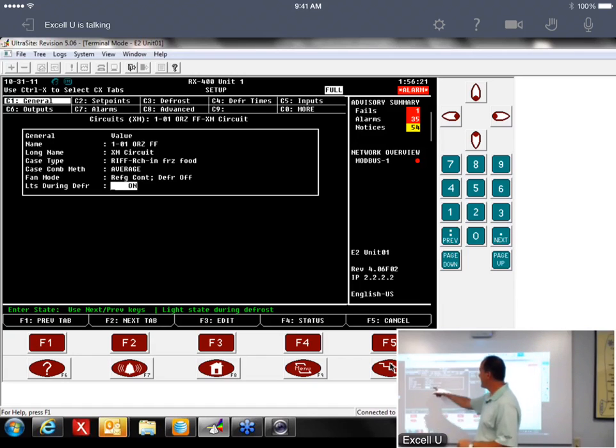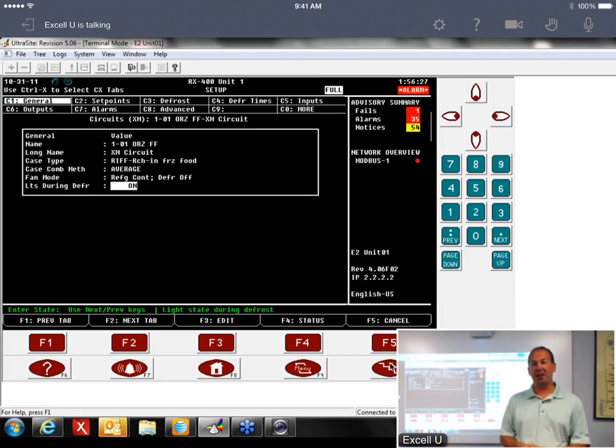Lights during defrost defaults to off, which means whenever it goes in defrost, it turns your lights off. There's a lot of customers that want the lights off in defrost. It tells the customer, hey, this is in defrost. Publix is not one of them. So anyway, we have to manually change that from off to on.